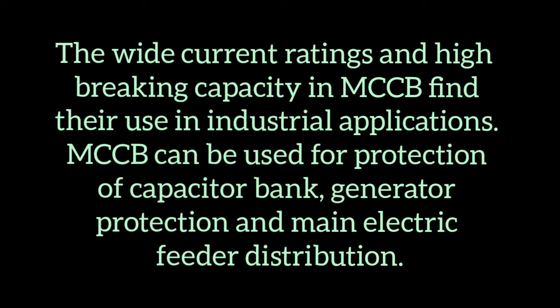MCCB can be used for protection of capacitor banks, generator protection, and main electrical feeder distribution. It offers adequate protection whenever an application requires discrimination, adjustable overload setting, or earth fault protection. So now we all know what is MCB and what is MCCB. Let's find out the difference between MCB and MCCB.